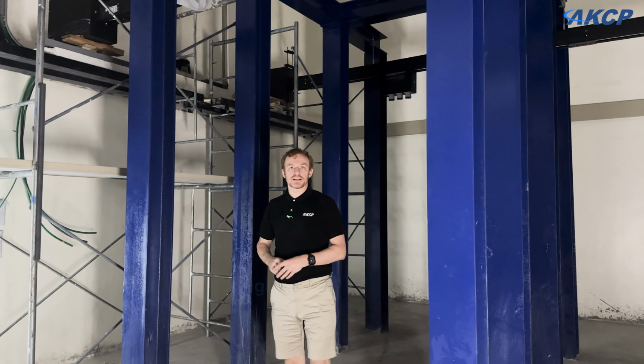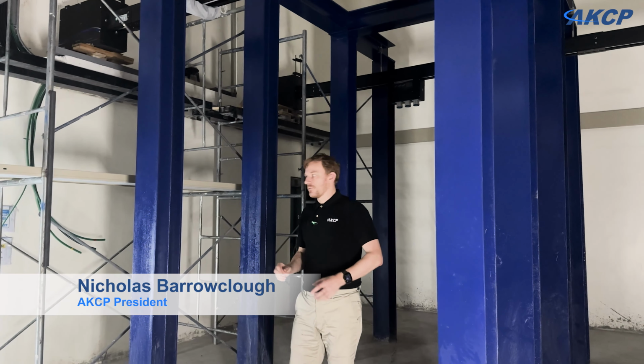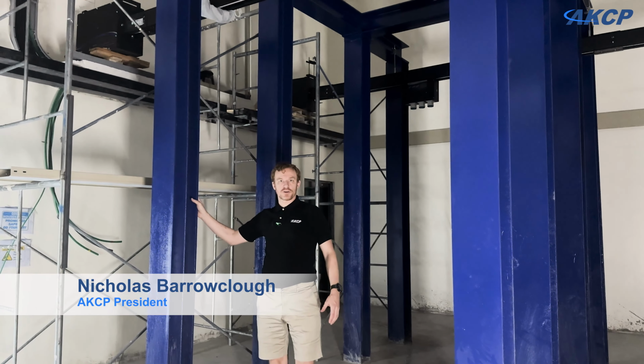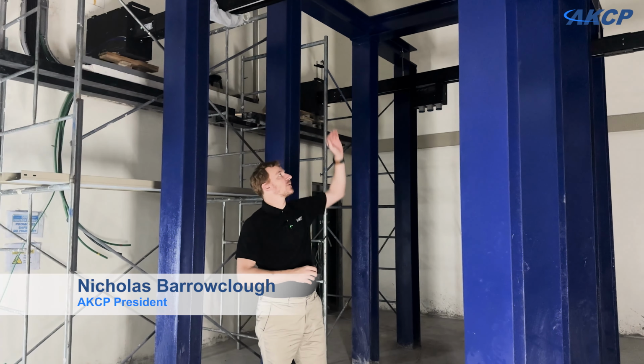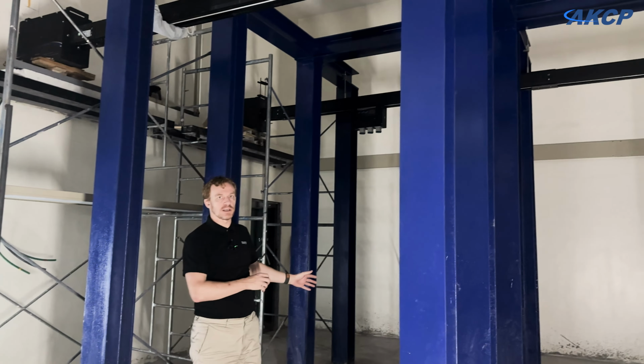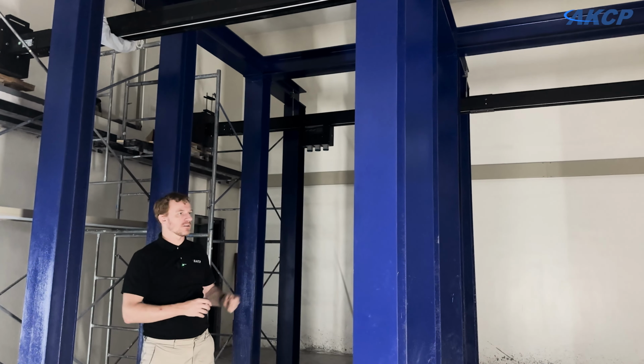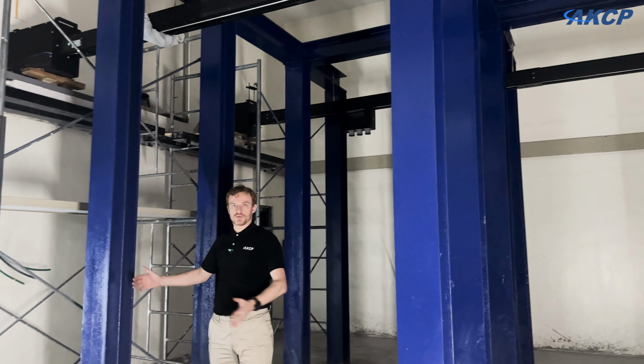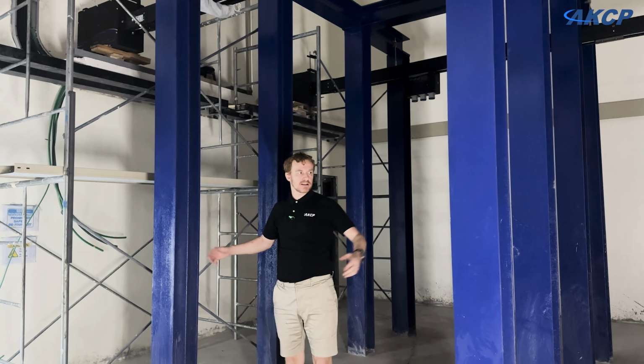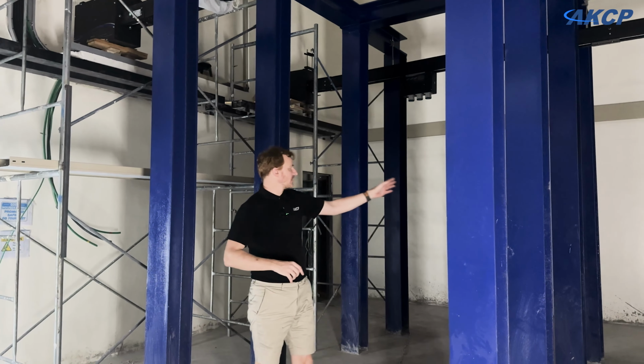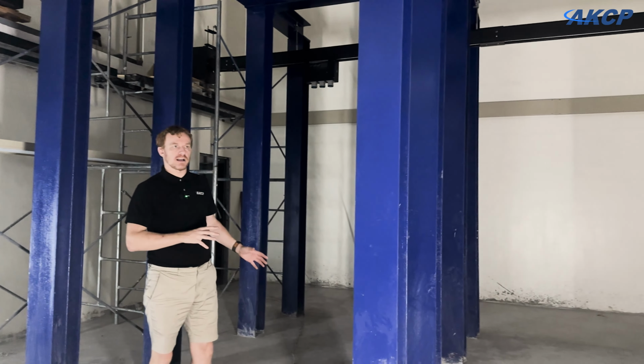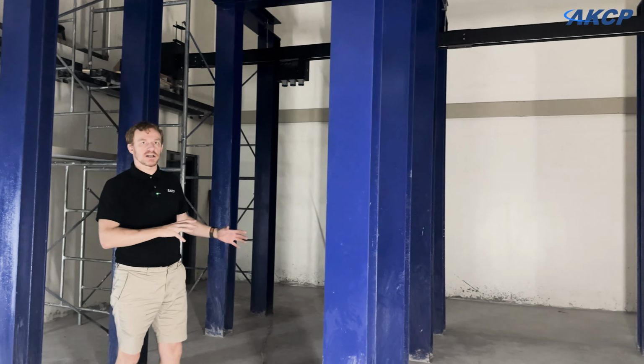So here I am in data center hall number 1, where we finished last year the steel structure, which is being used to hold up our overhead heat exchangers, which will be cooling air directly as it leaves the hot aisle. In between these columns, we've got space for 3 racks, so 3 and 3, then 3 and 3 - a total of 12 rack hot aisle containment pod, or 10 racks together with 2 in-row AHUs.